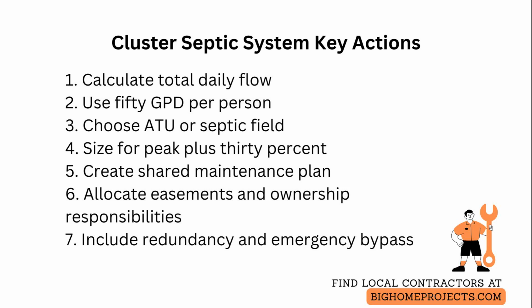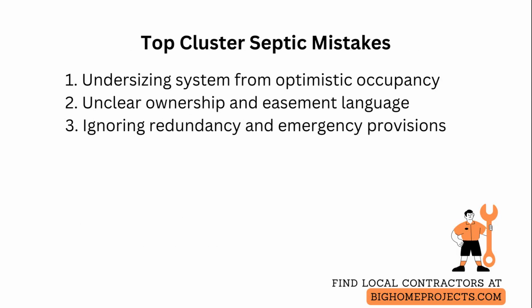Ensure the design conforms to local cluster development rules and obtain permits early because modifying a built system is costly and time-consuming. Common mistakes include undersizing the system due to optimistic occupancy estimates, which is avoided by using conservative per-person flow numbers and sizing for total possible occupancy.